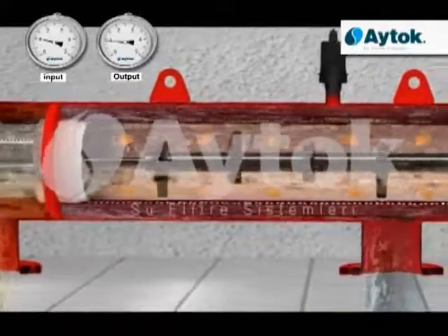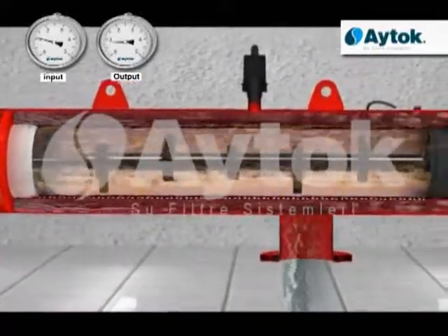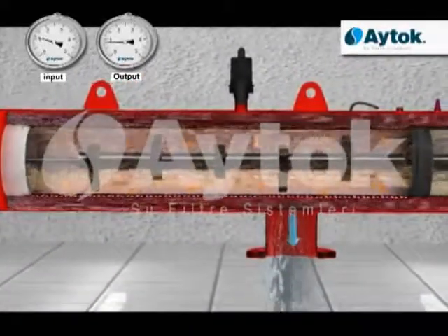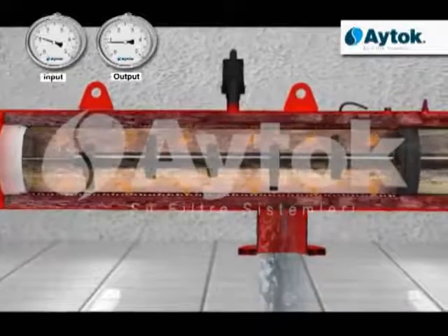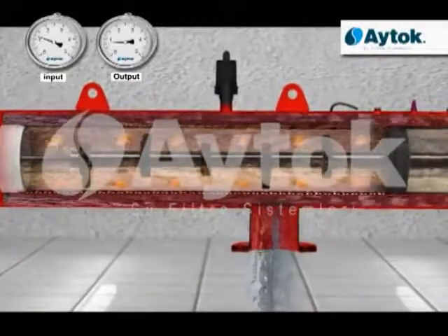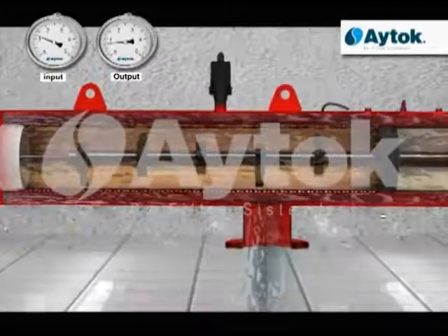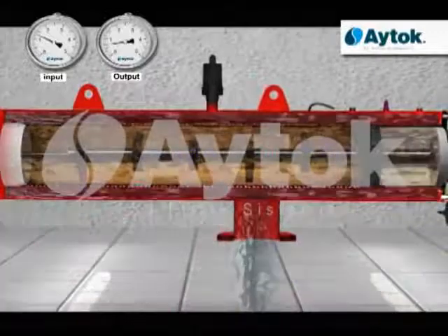The particles in the water that goes to exit from the internal part of the fine sieve, which is protected by a tough and spaced sieve, constitute a dirty layer on the inner surface of the filter. When the pressure arising from the layer reaches the values determined previously, a backwashing operation starts for cleaning of the fine sieve.